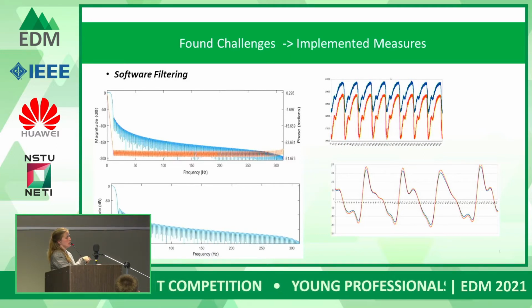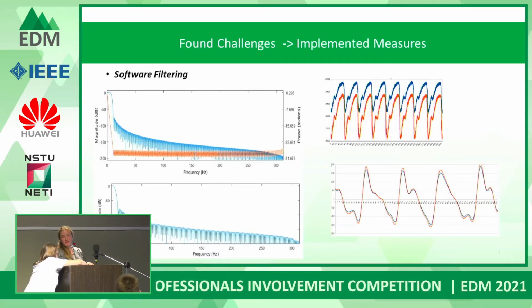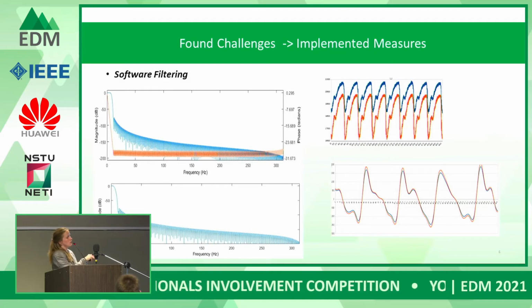Then after the signal goes through the low pass filter, it becomes available for monitoring the plethysmogram, but it is not enough filtering for the further Fourier transform, which is for pulse extraction. So we also need the bandpass filters shown on the downside. And after that, we need a special lattice filter, which is indeed an adaptive noise canceller, which helps us provide the correct saturation extraction.